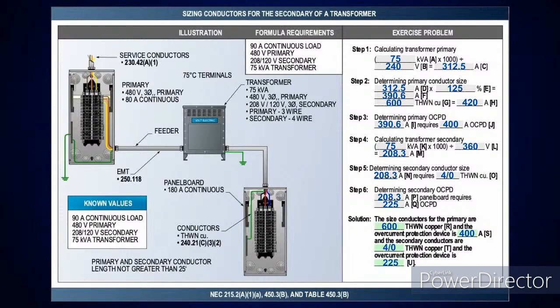And here's a good one, and this gives you a little off thing here. If you look at the secondary, I've got a 75 kVA transformer, and I've got a 208 volt secondary, and it's 3-phase, so I'll take it at 1.732, and that's going to give me 360 volts, which will give me 208.3 amps. And if I go look at table 310.16, the next size above that in the 75 degree C column is 230 amps, which is a 4/0 conductor. So if I have 208.3 amps for the panel board right there, what size overcurrent protection device would I need?